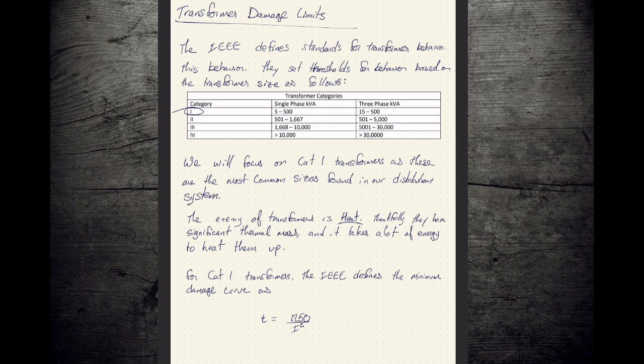So the enemy of transformers, the number one enemy is heat, right? So what kills a transformer? Insulation failure. What kills insulation? Getting it too hot. Now, under fault conditions, there is a second thing that goes on. Those very high current flows that we're seeing, well, when you have magnetism, if you've ever held magnets together, tried to force two North Pole magnets together or pull apart a North and a South Pole magnet, there's a physical force there. Magnetism tries to move things.